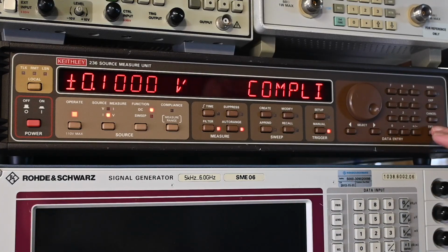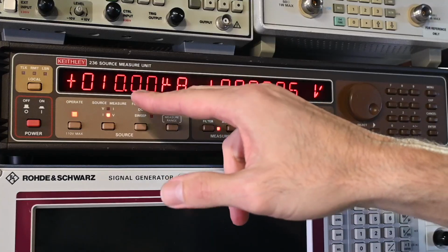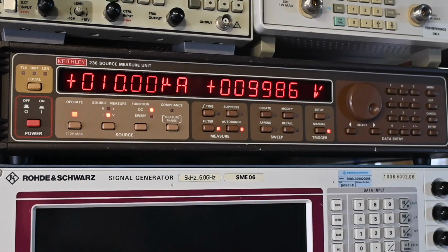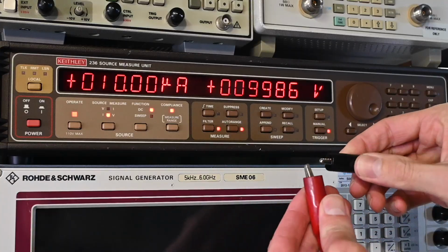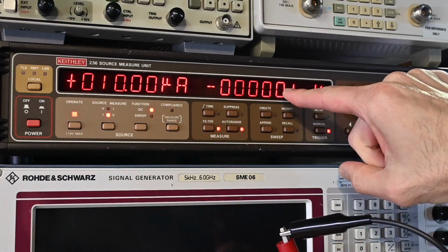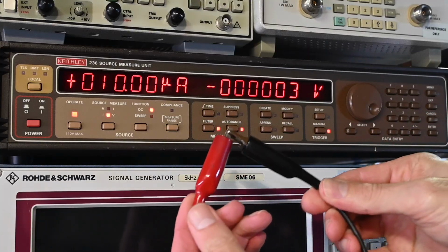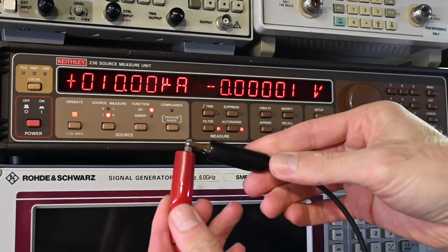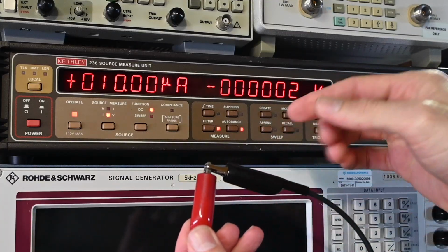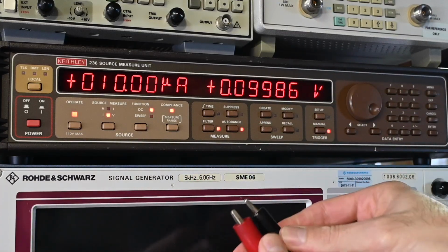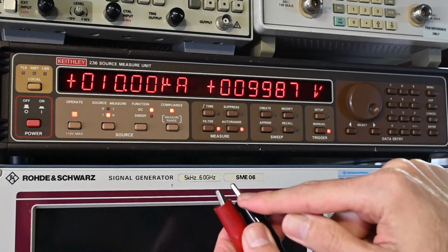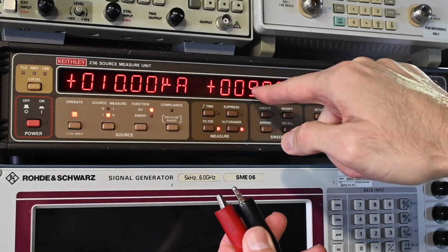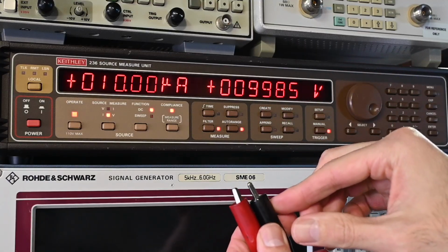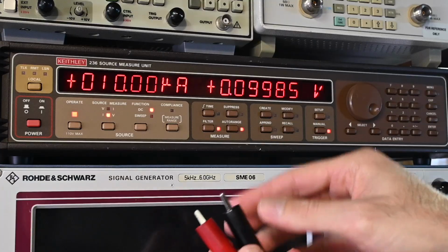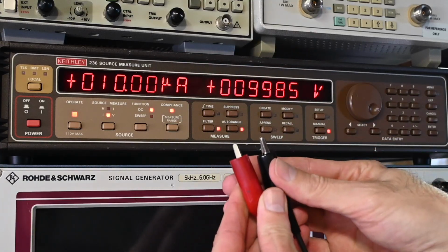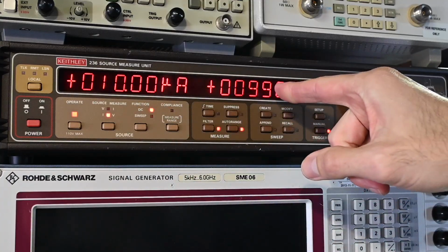What that means is that even though this is trying to do a constant current of 10 microamps, the ends of the test leads are not connected right now. If I connect them like this, you can see the voltage essentially falls to 0. Now 10 microamps is flowing through the wires in the test leads, but the voltage is essentially 0 because there's no resistance. But if I open this up, now the voltage across these test leads is just shy of 100 millivolts, 0.09985. That's again the compliance voltage, and it's trying to do 10 microamps, but no current is actually flowing. All right, so this is the set value, this is the measured value over here.